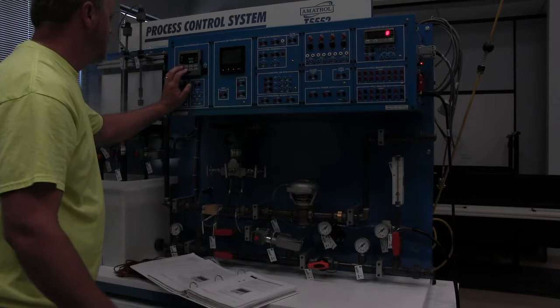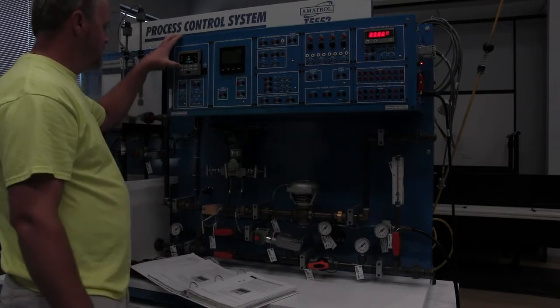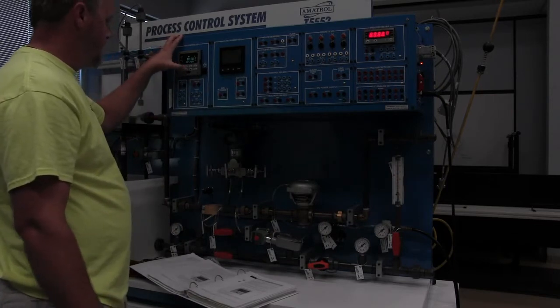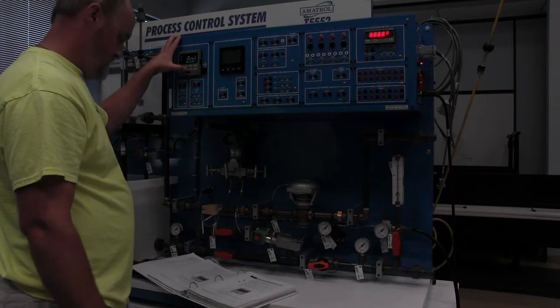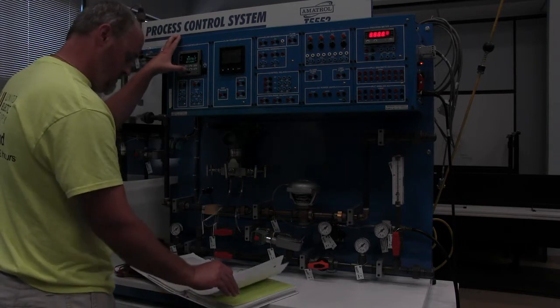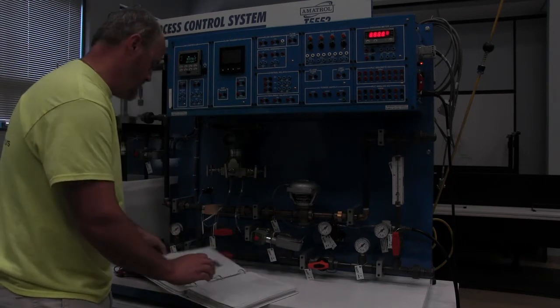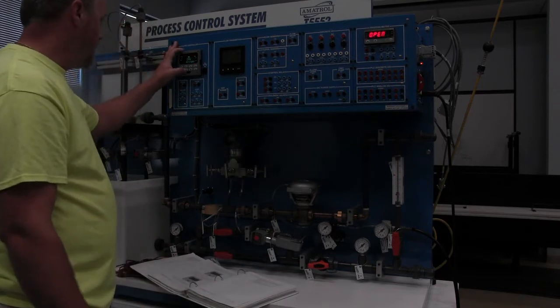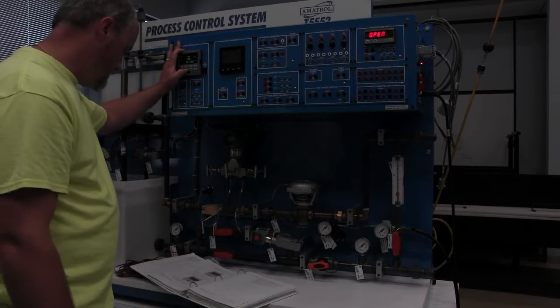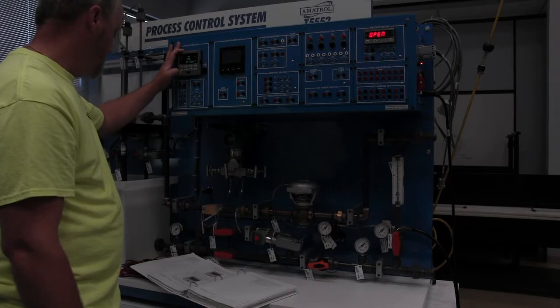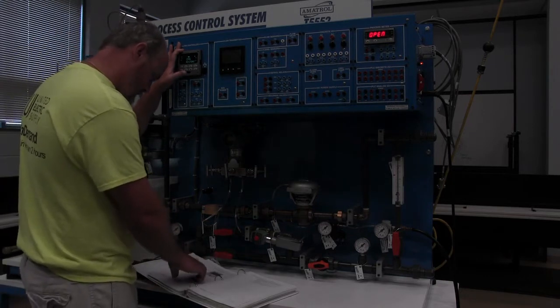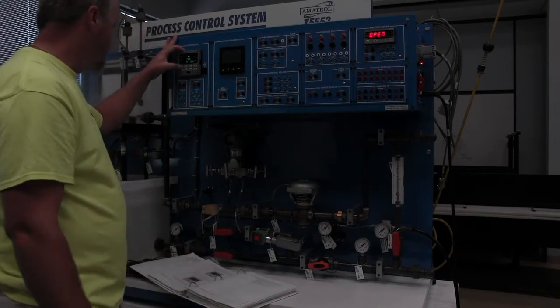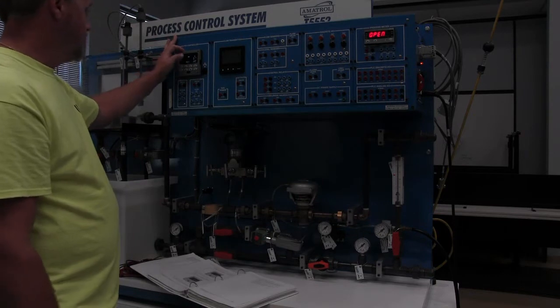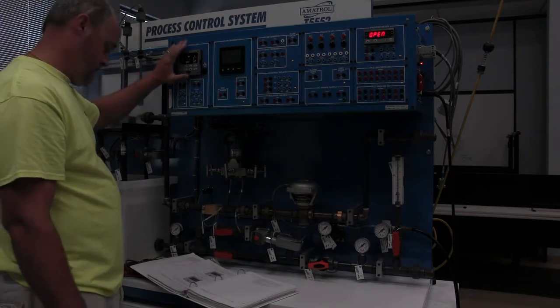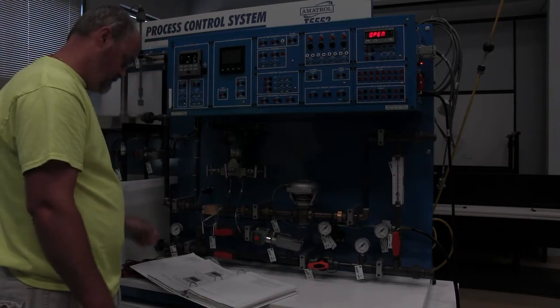Turn it on, press and hold. Update comes up, we're going to press the function loop key. It's going to say restore disabled. When it says restore disabled, we are actually going to hit the up arrow until it says configure. Once it says configure, which it does, we're then going to press the function loop key, and it's doing a restore. So now this unit is factory restored.